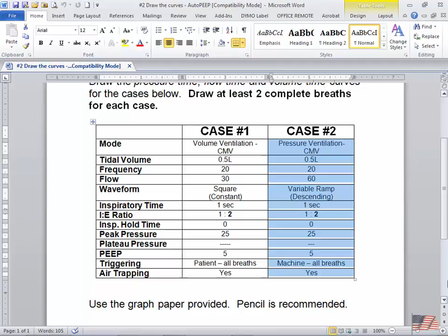Okay, now let's see how I would go about doing this if I... No. Let's do this if it's a pressure-based breath. Okay. So it's all machine breaths, a peak flow of 60, a frequency of 20, 1 second I-time, okay, 5 and 25. So here we're going to start with the pressure tracing. Because I have a pressure-based breath, I'll go ahead and make 10, 15, 20.